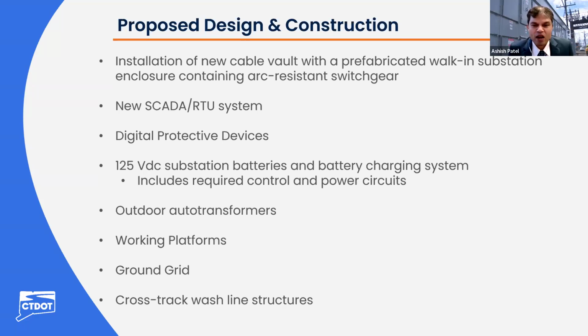The newer substations are unmanned and all circuit breakers are controlled from a remote location. In this case, the remote location is considered to be the Grand Central Terminal. The SCADA system, also called the supervisory control and data acquisition system, will be designed for controlling and monitoring the balancing substation from the remote location. The digital protective relays are state-of-the-art, reliable, easy to program, and easy to maintain, and will be designed under this project. The 125-volt DC station power will be designed and a battery system will be used under this balancing substation.